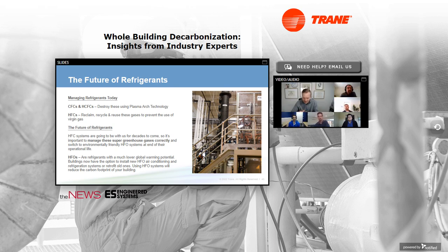Absolutely. If you have a chilled water load all year round—data center, data closets, maybe a process cooling load—anytime you have a simultaneous heating load, you could use that rejected heat, call it heat recovery, to offset some or all of your heating load. Looking at the operational levers we can pull, energy efficiency is typically first, and one of the easiest forms of electrification is heat recovery, because you already have those BTUs in your building. Instead of throwing them outside, let's repurpose them and offload some of our other equipment.